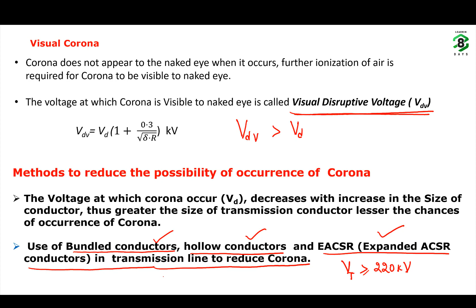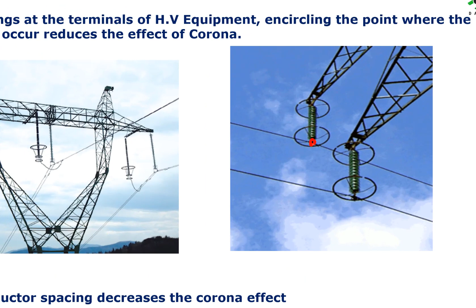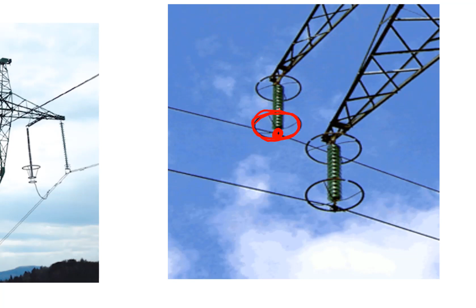Using corona rings at the terminals of high voltage equipment, encircling the point where corona is likely to occur, reduces the effect of corona. At high voltage points where corona is likely to occur, we give more surface area at that point so that the electric field intensity is uniformly distributed or reduced. So by providing corona rings, instead of keeping a single point, I am providing a ring. So the overall size of that point increases, the electric field intensity of that point reduces, and thus the probability of occurrence of corona reduces.